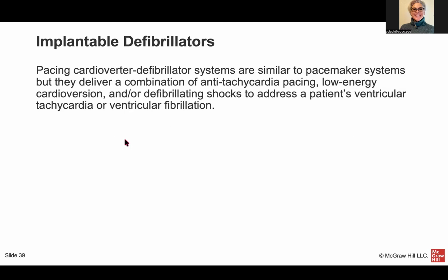Implantable cardioverter defibrillators, or ICDs, are similar to pacemakers, but serve a different, more urgent function. A pacemaker manages abnormal heart rhythm by pacing. An ICD does that too, but also monitors for life-threatening rhythms, ventricular tachycardia or ventricular fib.